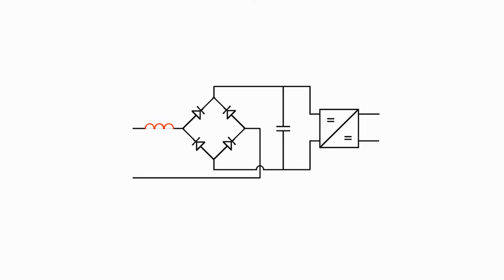Because of the inductance of the coil, the current that charges the capacitors will take a little bit longer to ramp up. At the same time, when the voltage goes down again on the grid, the current will take a while to decay because of that inductance. So the inductor will spread out the current a bit more, make those spikes less sharp, and improve the power factor of the system.